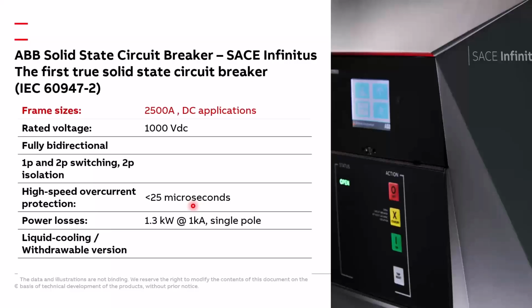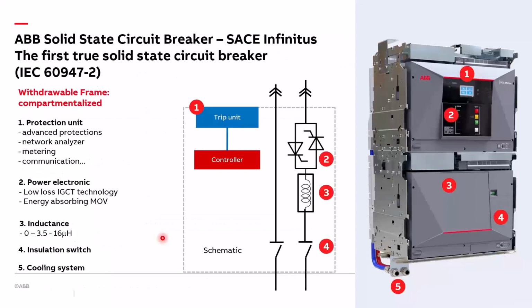semiconductor. Then the current goes to zero through the so-called metal oxide varistor installed in anti-parallel to our semiconductor, in order to limit the overvoltage and to allow the current to go to zero in a smooth way. The power losses are very much lower compared to other technology, which usually is up to 4 or 5 kW. It is a liquid-cooled version in order to limit the space and the total volume of this circuit breaker. And here you can see the schematic of the internal architecture.